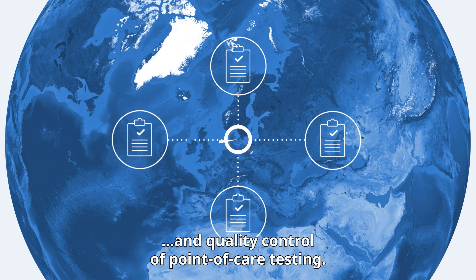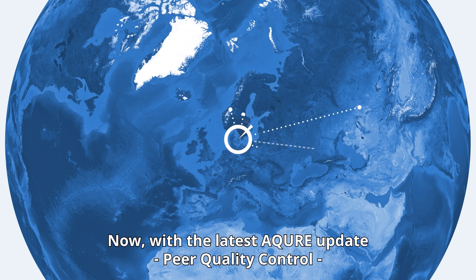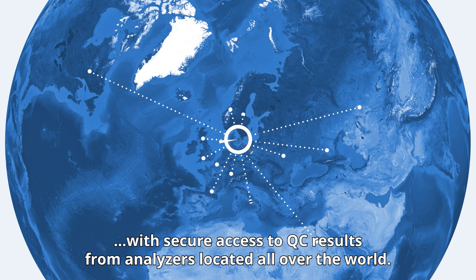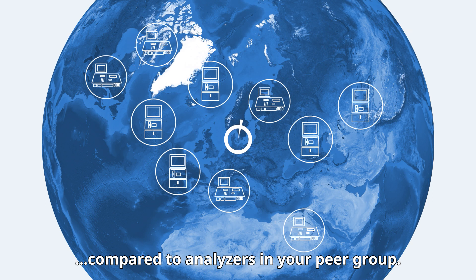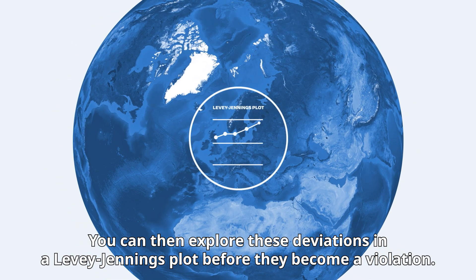Now with the latest AQURE update, peer quality control, you can further improve analyzer performance with secure access to QC results from analyzers located all over the world. AQURE supports you in your daily management by distinguishing statistical deviations compared to analyzers in your peer group.